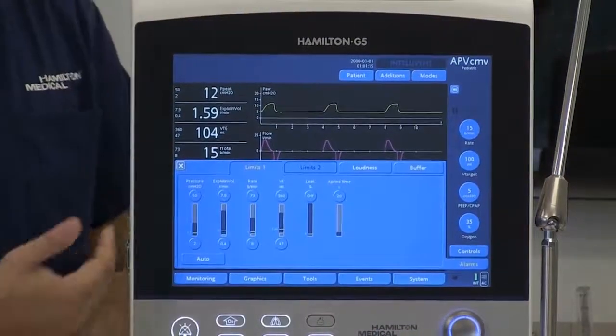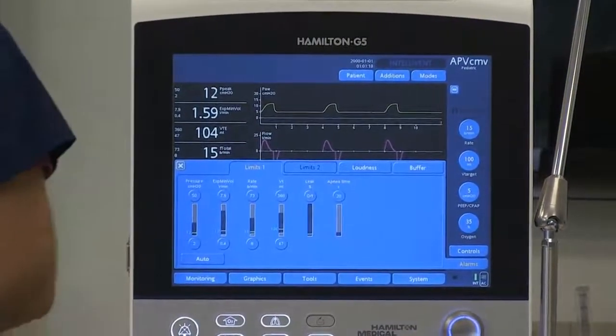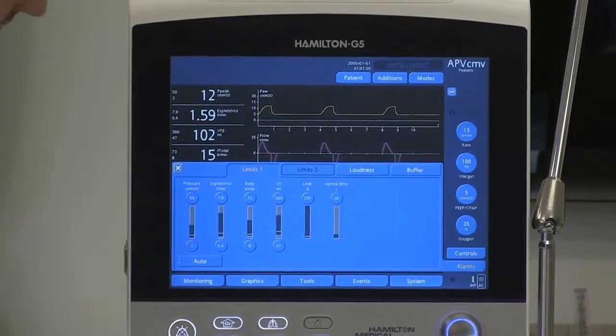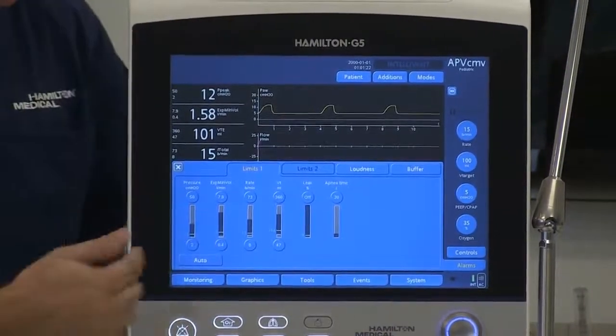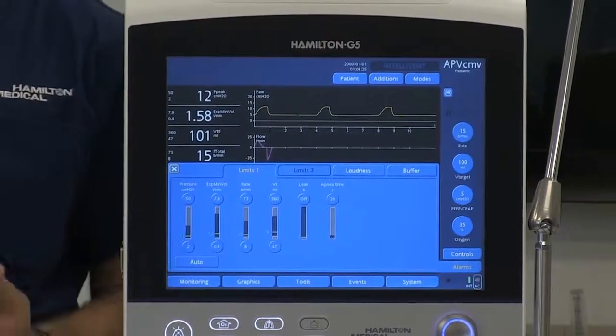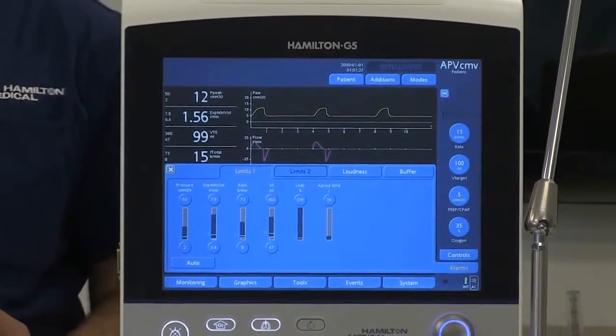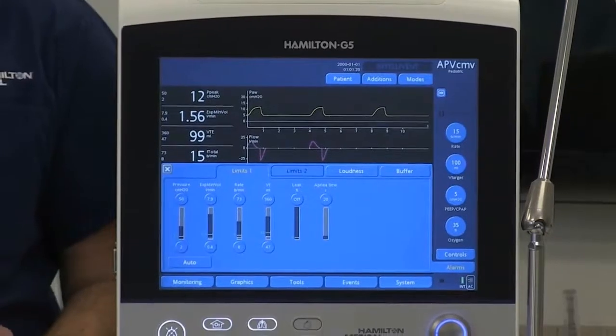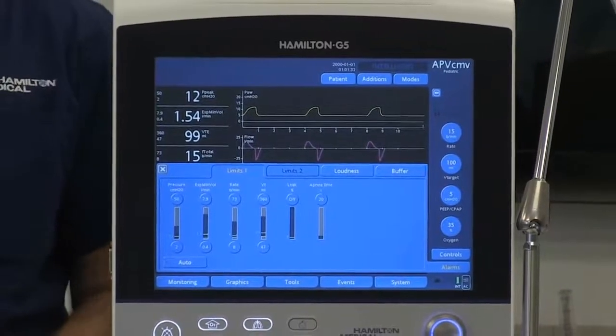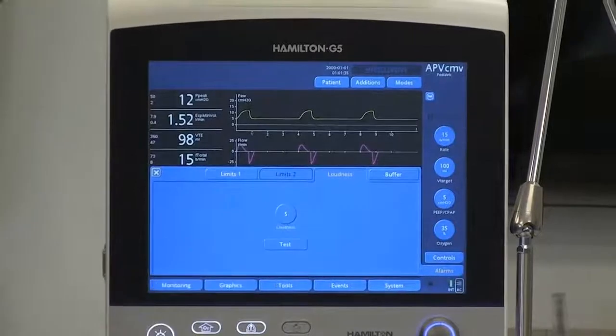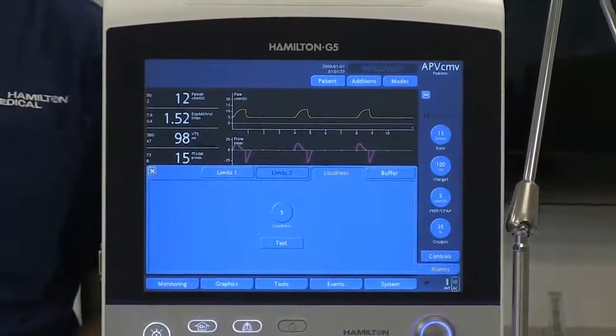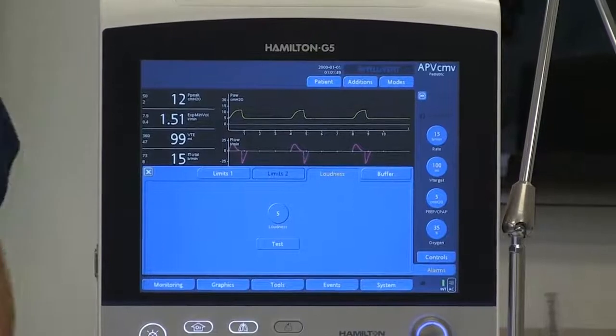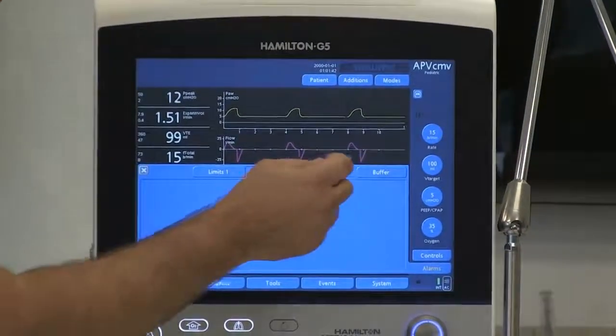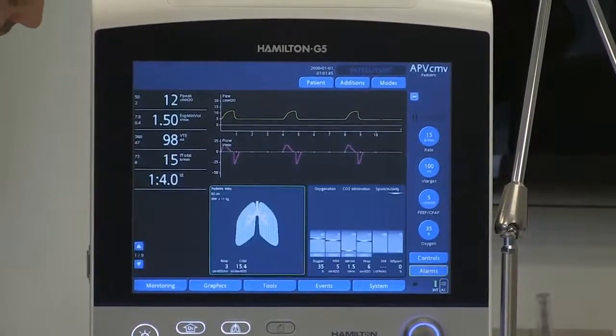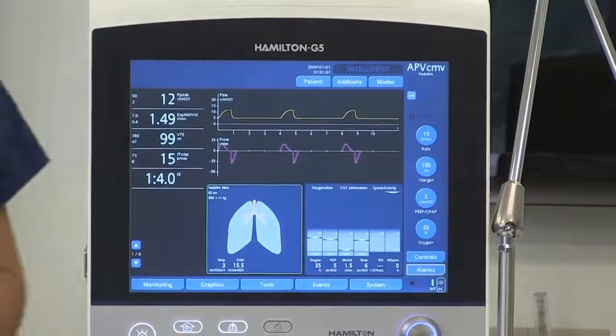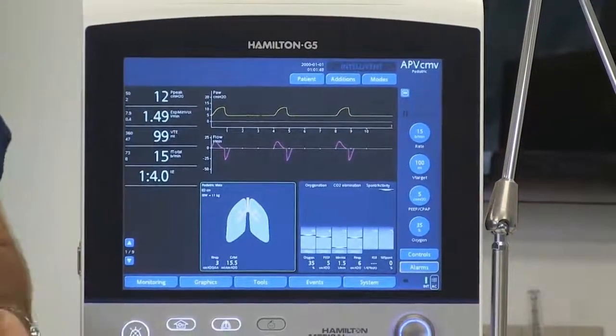Alarms. This is where you'll find your alarm parameters section. The green floaters and the green numbers on each column indicate what the patient is actively doing at this moment, making it a little bit easier to set your alarm parameters around what the patient's doing. In the loudness section, you can adjust the volume of your ventilator alarm, going from 1 to 10. Again, you can close any screen by hitting the X at the top left-hand corner of the box.